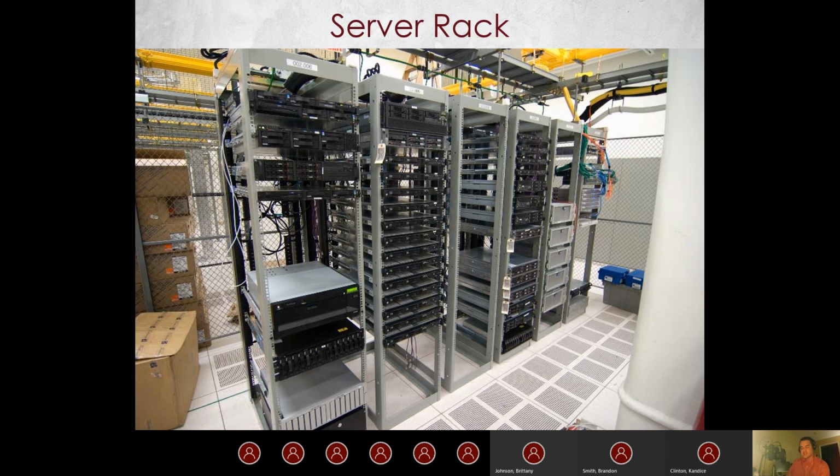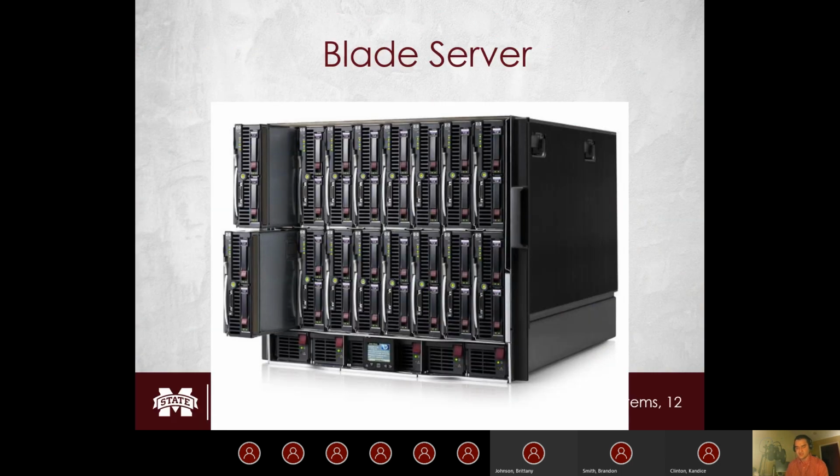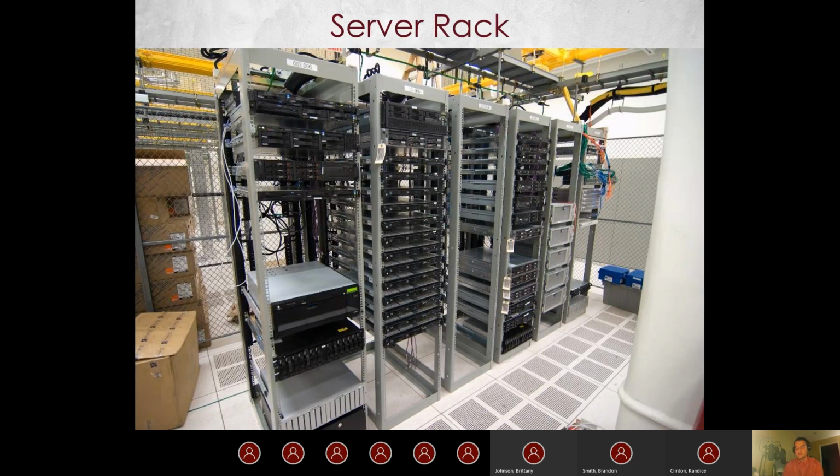And servers are kind of unique in that they're sized out by what's called a U. It stands for unit. Each U is actually going to be 1.75 inches tall. So we have several 1U servers, and then we could also have a 2U. Looks like right here, toward the bottom, there's actually a 2U, which would be 1.75 times 2, which is 3.5 inches. Whoops, didn't mean to click there.